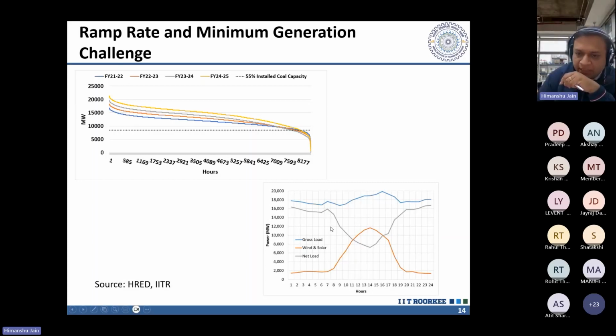Now the challenge this creates is a very sharp down ramp. You can see the power going down from 16 gigawatts all the way down to around 7 gigawatts - a 9 gigawatt drop in 6 to 7 hours. Then it goes back up in the evening time to around the same levels. So you need resources that can quickly ramp up and then quickly ramp down in order to meet this kind of variability that solar is going to induce in the system.